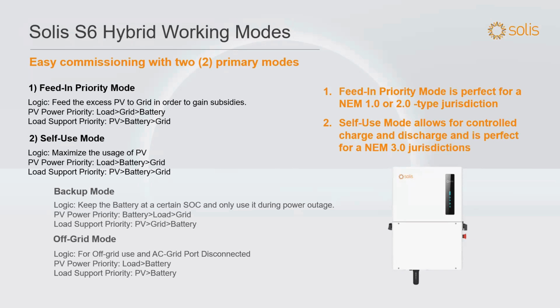When you're commissioning this kind of inverter as opposed to a regular grid tie inverter, remember, a regular grid tie inverter really only has one operating mode, one primary mode, and that's feed-in priority. When it's getting solar, it's feeding the loads, and as soon as the loads are satisfied, it starts feeding into the grid. You can set this hybrid inverter up for standard feed-in priority mode too, and that's how it will act, just like a regular grid tie inverter.